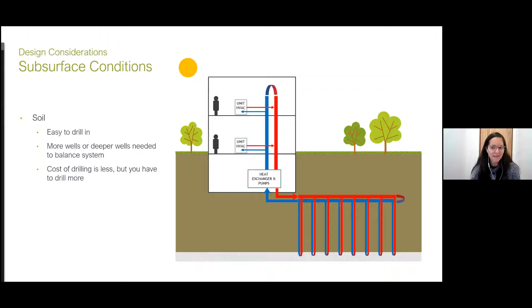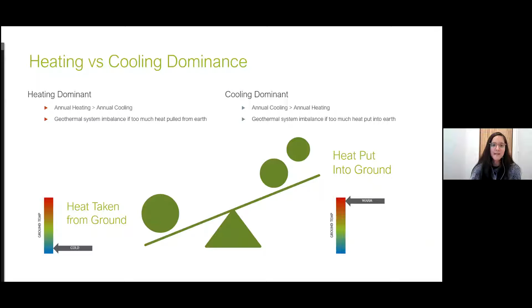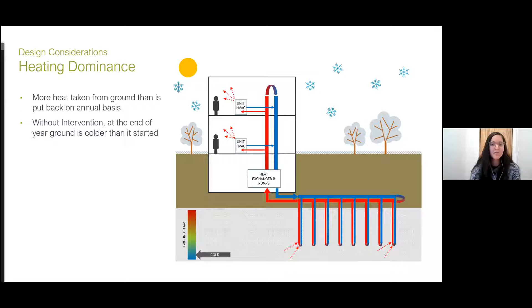The next thing you take a look at, once you understand what the earth can provide you, is whether your building is considered a heating or a cooling dominant building. A heating dominant building is a case where more heat is taken from the ground than is put in on an annual basis, and without intervention, at the end of the year the ground will end up being a bit cooler than what it started.